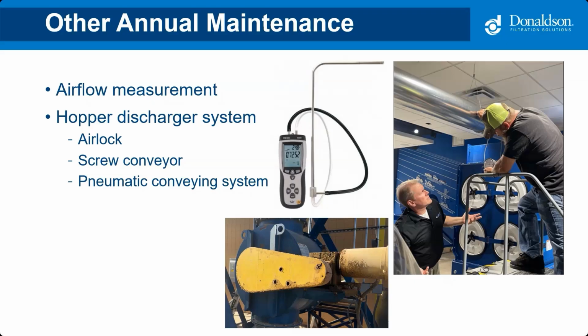Hopper discharge system. I mentioned that as part of the monthly and quarterly maintenance already. So as you're checking that once a year, you want to go deeper on those systems like you did with the fan and motor. And now you're checking for proper belt tension. We want to check oil level and lubrication, any grease zerks that might be in the system. Again, you're already checking periodically for leaks. So this is just once a year when you're going much deeper for more of the mechanical things, bearings, fan and belts, lubrication, things like that.